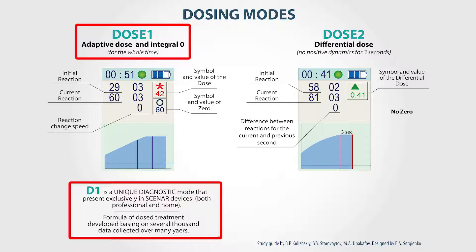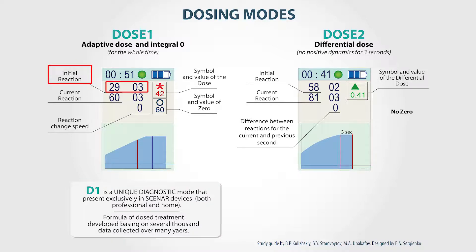The primary expert criterion is the value of reaction. When the electrode is applied to the skin, the value of initial reaction appears and stays on the screen. If we take the device off the skin, this value will remain on the screen.